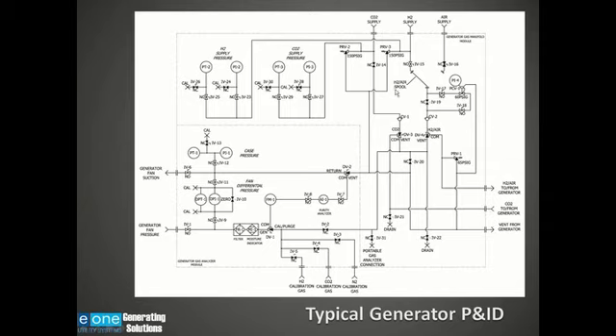Notice this spool piece right here. This is used to prevent air and hydrogen being put in the generator at the same time. It will not eliminate it. You need to have proper standard operating procedures so that a mistake isn't made and hydrogen and air are put in the generator at the same time. But this spool piece will certainly help minimize the chances of that happening.